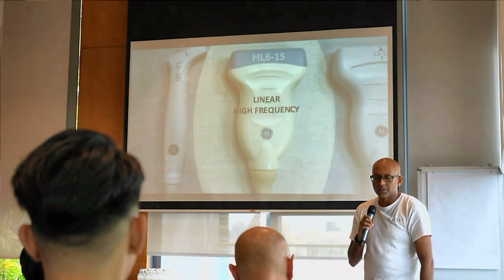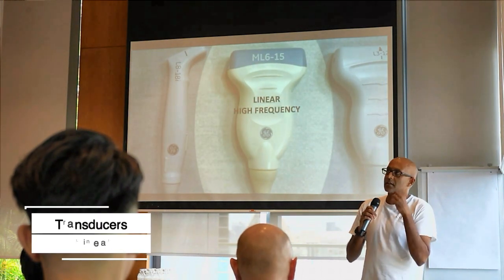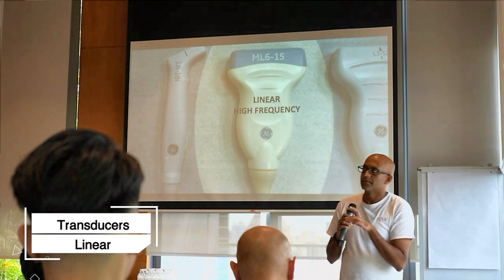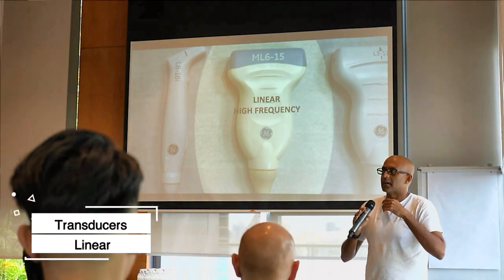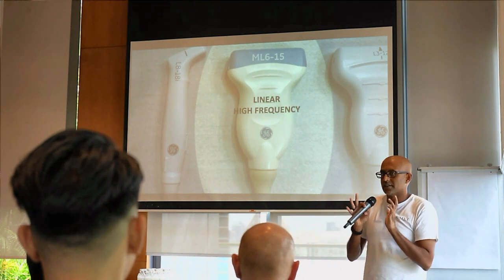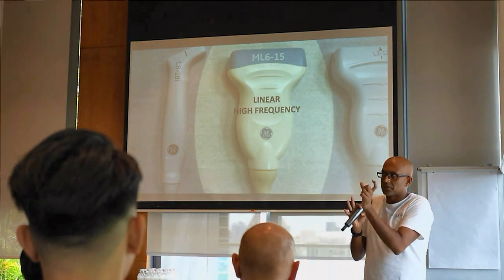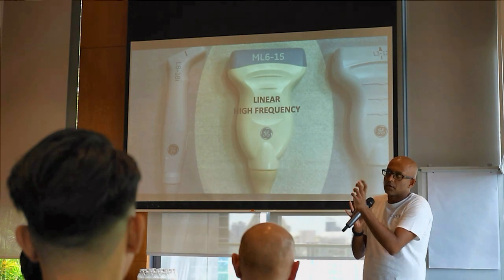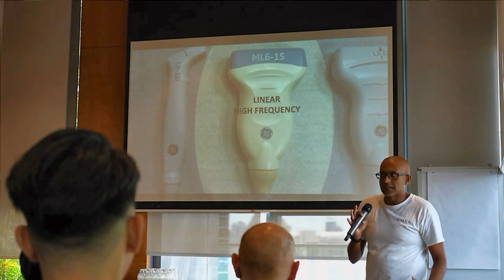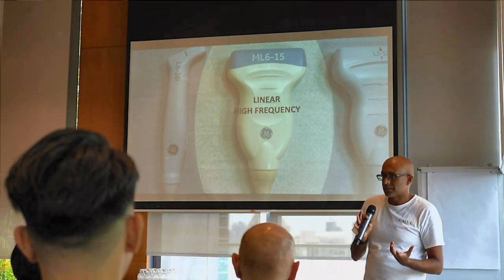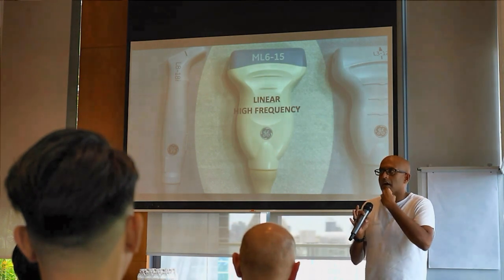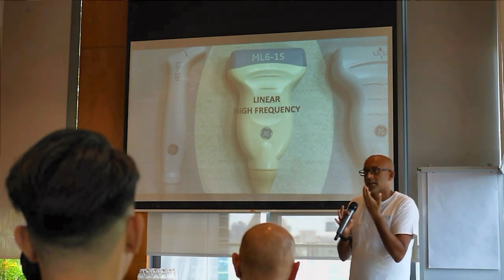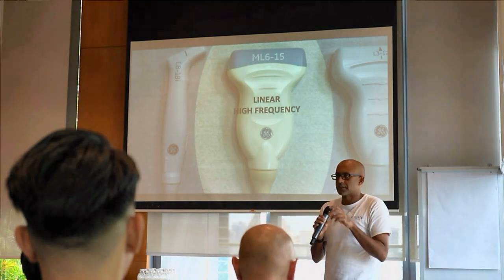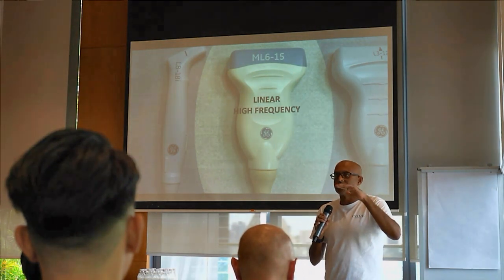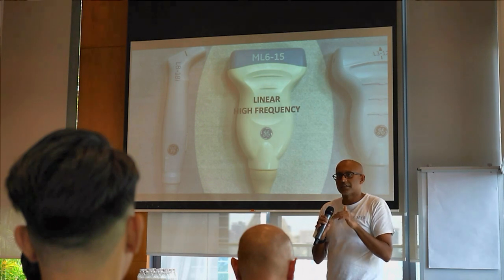Next, we have one of the linear transducers, and this is a higher frequency linear transducer. Now, there are some nuances to these things. Some of them have matrix, this, that, and the other thing. But essentially, this is good for things like shoulders, knees, maybe ankle joints as well. And it gives a high resolution, so 6 to 15 megahertz. A decent frequency, and it's a balance between frequency and penetration.